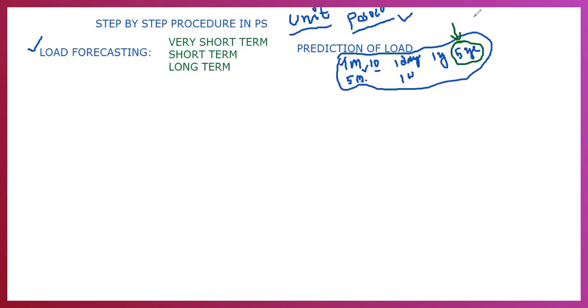Because long-term forecasting reveals that if there is a 100 megawatt load increment on the power system after 5 years, then from now onwards we need to start establishing the power plant, because the power plant takes time to establish. It depends upon the type of power plant — it may be a thermal, coal-fired, or hydel power plant — but approximately it will take 5 years to establish. So if after 5 years the load increment is 100 megawatt, in order to meet this we have to establish a new power plant, which takes 5 years. At the end of those 5 years, we will be in a position to meet this excess demand.